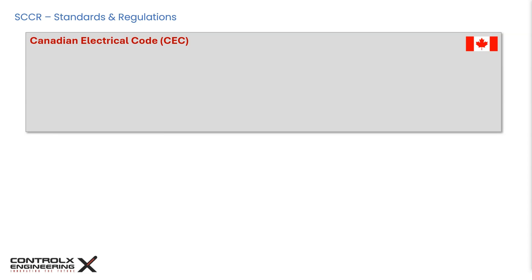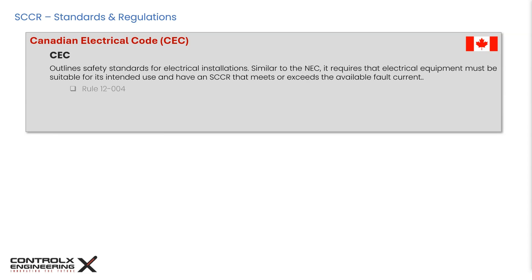The Canadian Electrical Code, or CEC, similar to the NEC, emphasizes the critical importance of considering SCCR in the selection, installation, and operation of electrical equipment. The CEC addresses SCCR in several key areas: Rule 12-004 requires that electrical equipment be suitable for the location and conditions of use, including withstanding available fault current; Rule 12-104 requires that switchboards, switchgear, and panel boards have an SCCR not less than the available fault current; and Rule 12-204 requires industrial control panels to be marked with their SCCR, unless they contain only control circuit components.